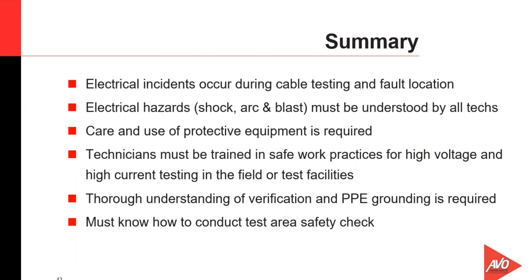We've had numerous fatalities where people have actually been thumped with a high voltage thumper. With a 1500 joule discharge unit, where it only takes about 6 joules of energy straight across the heart to cause heart fibrillation, a 1500 joule unit certainly has the capability of doing that. Most all of the test equipment that we use in medium voltage and high voltage power cable testing has the potential of creating lethal shock.